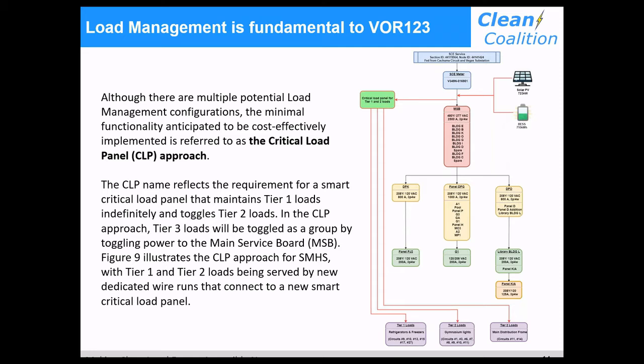What load management means is, if we're going to provide indefinite resilience for the tier 1 loads, we have to have the ability to turn the tier 2 loads off if they threaten the ability to keep the tier 1s on. And we have to be able to turn the tier 3s off to keep the tier 2s on as long as possible, and the tier 1s on forever. There are multiple ways to accomplish load management, but I wanted to touch on it because it is absolutely critical.